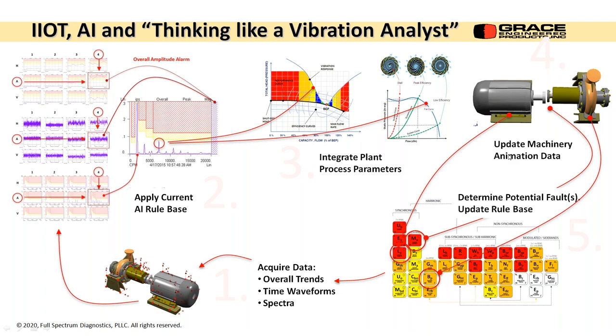So depending on what kind of net of transducers we have, we can get some decent animation. And then even applying a rule base for potential faults. So maybe this is moving like this, but it's not high enough amplitude that it's an issue yet. We can still say, hey, here's our potential problems. We might have a loose foot or a soft foot. We might have a misaligned coupling, and we might have some blade pass frequency problems that are showing up. And then we apply that and get a better idea of where we sit statistically and then start the process over. So it's doing this not 12 times a year, but every hour, every minute, you're getting an update and a better idea of what your machine's trying to tell you, if it's hurting or if it's fat, dumb, and happy.